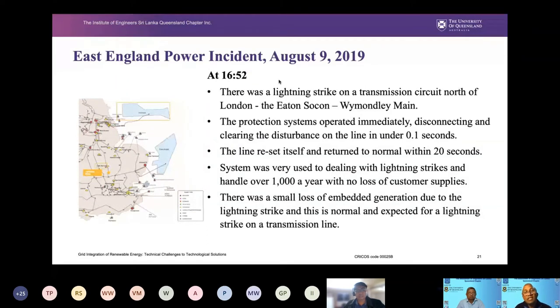And at about 16:52, again there was a lightning strike on the transmission line, which took the circuit out in the middle of the East England system. Then the protection system operated immediately, disconnecting and clearing the fault within 1 second. And the line reset again and returned to normal within 20 seconds.